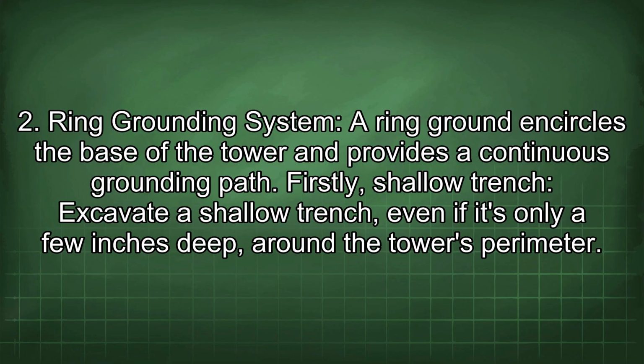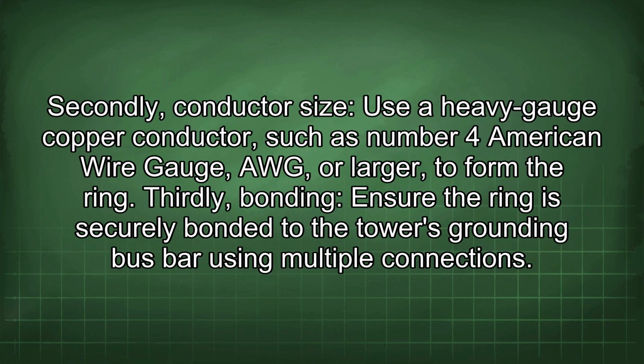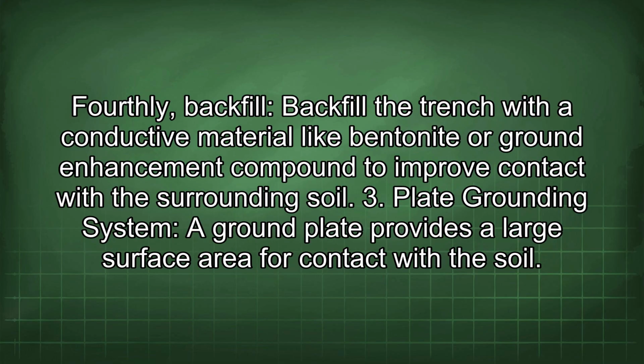2. Ring grounding system. A ring ground encircles the base of the tower and provides a continuous grounding path. Firstly, shallow trench. Excavate a shallow trench, even if it's only a few inches deep, around the tower's perimeter. Secondly, conductor size. Use a heavy gauge copper conductor, such as number 4 American wire gauge, AWG, or larger, to form the ring. Thirdly, bonding. Ensure the ring is securely bonded to the tower's grounding bus bar using multiple connections. Fourthly, backfill. Backfill the trench with a conductive material like bentonite or ground enhancement compound to improve contact with the surrounding soil.